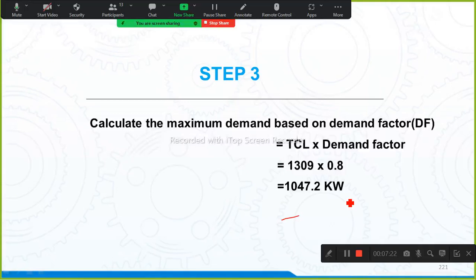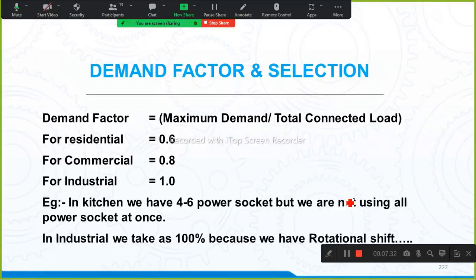Considering all these parameters, what is demand factor? Demand factor is defined as the maximum demand, that is the maximum used load, divided by the total connected load which you had provided. Generally people give separate demand factors for lighting and power. Averaging all these for a residential building, we take the total demand factor as 60%. For a commercial building, we take the demand factor as 80%, and for industrial, we take it as 100%. So what do 60%, 80% and 100% mean?